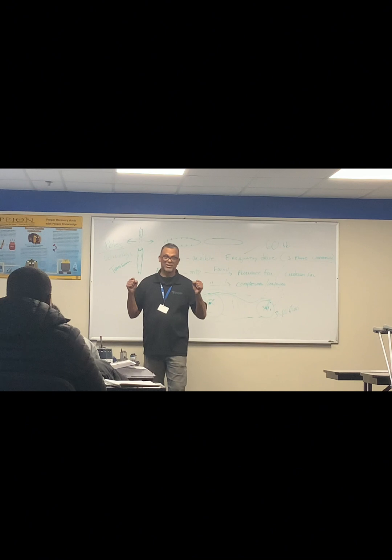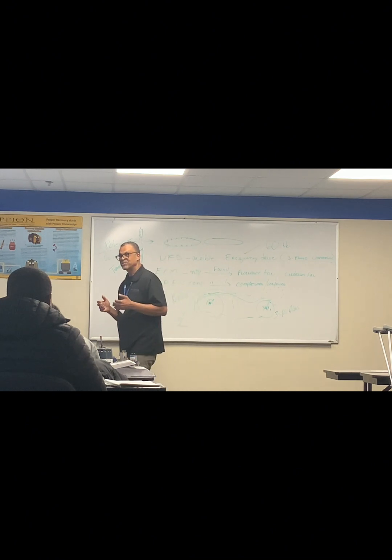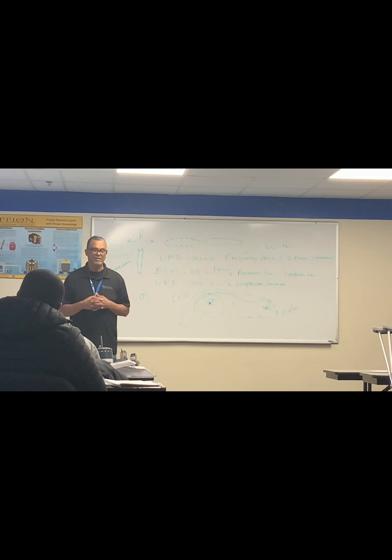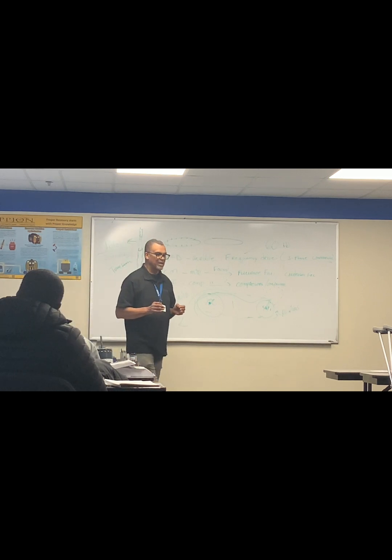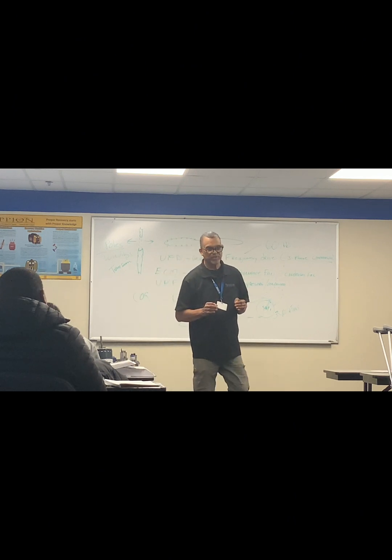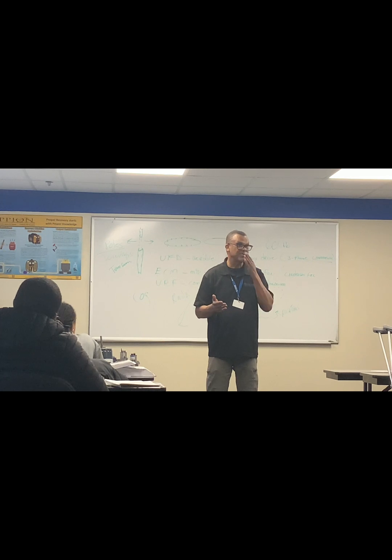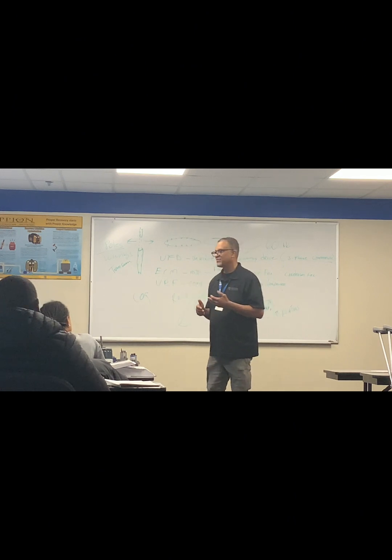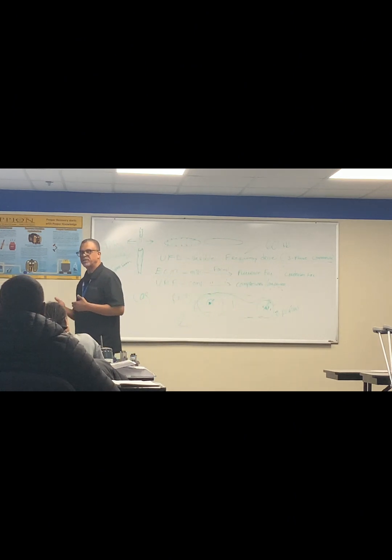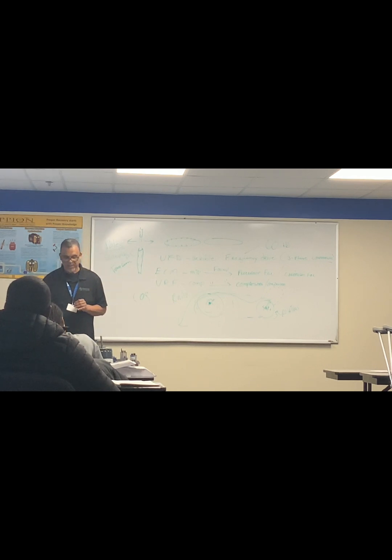I guess if a person can pull it like this in a strongman contest, it might move a little bit, but I doubt it. I'm just using that as a fictitious example. When you have a load, you have to match the motor's capabilities and specs to deliver the speed, the CFMs, cubic feet per minute, and the feet per minute for that particular motor. And it's designed on what we are using it for. A lot of times it changes, and that's why some of those frequency drives are kind of cool, because they can adjust that speed.